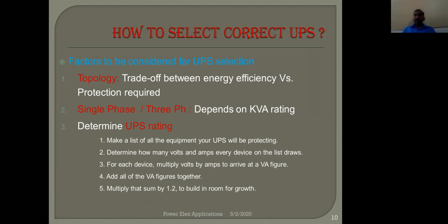If it is designed very cut to cut, then during transients or changeovers, due to heavy inrush currents or due to surges, two things can happen: if it's overloaded, your UPS will trip, and if there are surges, it will damage something, mostly your loads. So in order to protect your loads and protect your UPS from overloading, we have a factor of 1.2, means 120%, or 125% in practice. And this will determine your UPS rating.